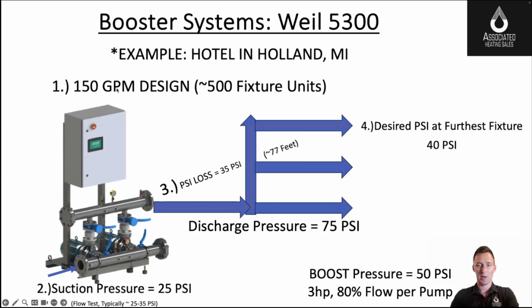This is our example that we helped with in Holland, Michigan. It's a hotel. We need 150 gallons a minute with our 500 fixture unit hotel. We know we're getting 25 PSI from the city on the suction manifold. Again, we're monitoring that here. We're also monitoring the discharge pressure. If we get total lack of pressure here, we have an alarm. Or if we're pumping against no head at all, we're getting an alarm. We have a lot of built-in alarms in these systems, which are pretty standard across the industry.